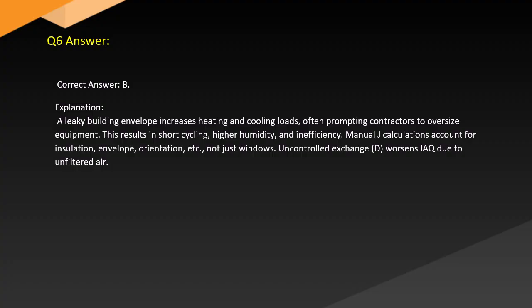Answer. Correct answer: B. Explanation: A leaky building envelope increases heating and cooling loads, often prompting contractors to oversize equipment. This results in short cycling, higher humidity, and inefficiency. Manual J calculations account for insulation, envelope orientation, etc., not just windows. Uncontrolled exchange, D, worsens IAQ due to unfiltered air.